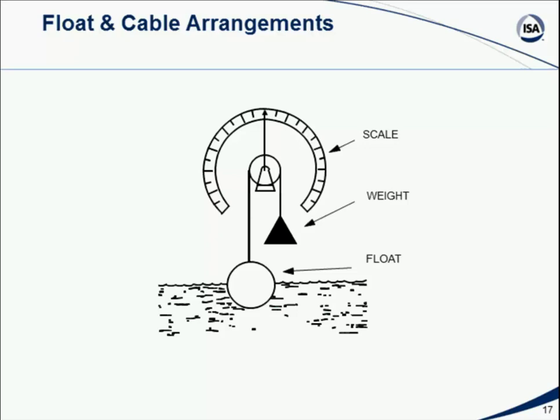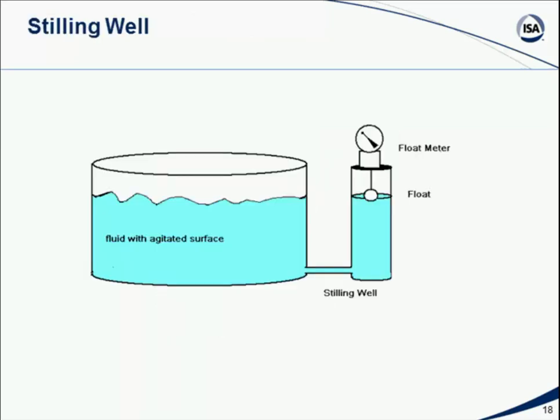As the fluid level goes up or down, the float will rise and fall, counterbalanced by the weight, and the pulley has a pointer on it. So as the fluid level goes up and down, the float goes up and down, which pulls the cable, which causes the pointer to turn left or right, indicating the level in the tank. Well, that's the basic principle of a float cable arrangement. In reality, there are designs that use this concept, but are not exactly built this way.